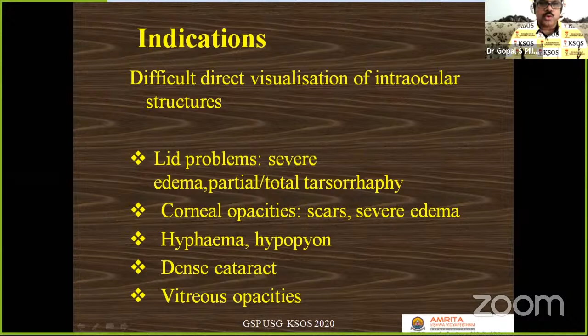The frequency of the ultrasound that we use for the abdomen is about 2 megahertz. For the posterior segment it is about 10 megahertz. And for ultrasound biomicroscopy, we use 50 to 100 megahertz. The higher the frequency, the lesser the penetration, and the greater the resolution. That is how the resolution of an ocular ultrasound is somewhere around 800 microns, whereas that of a UBM is about 50 microns.